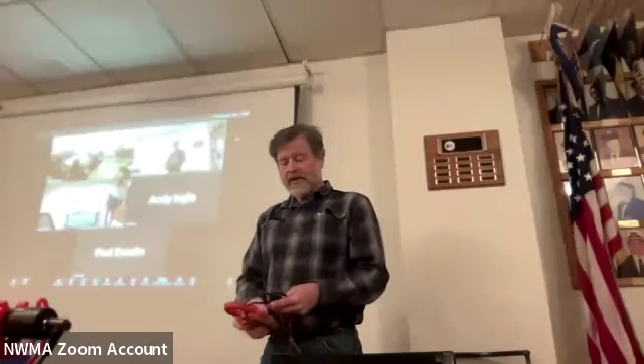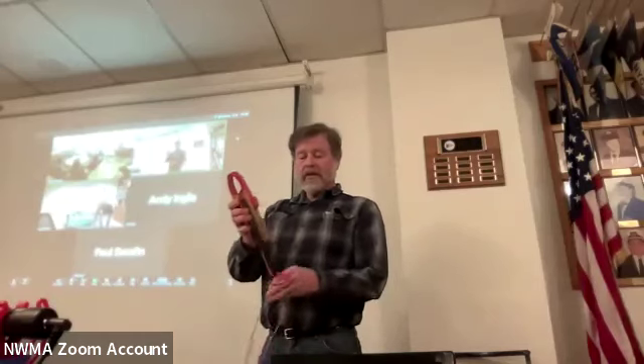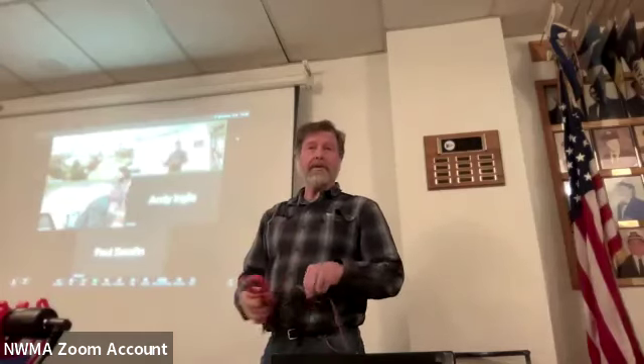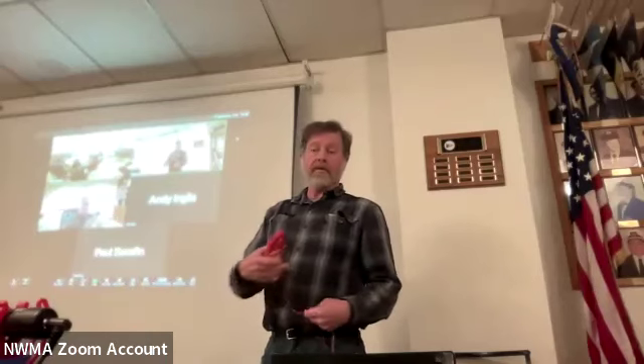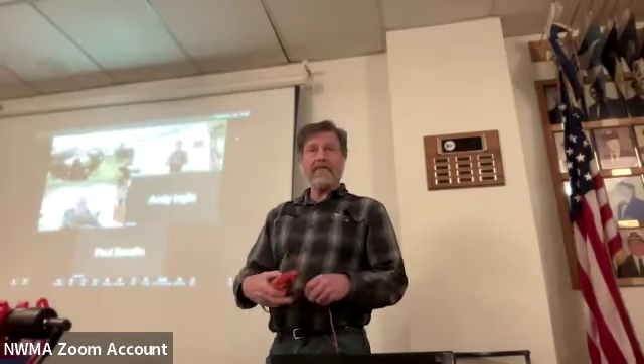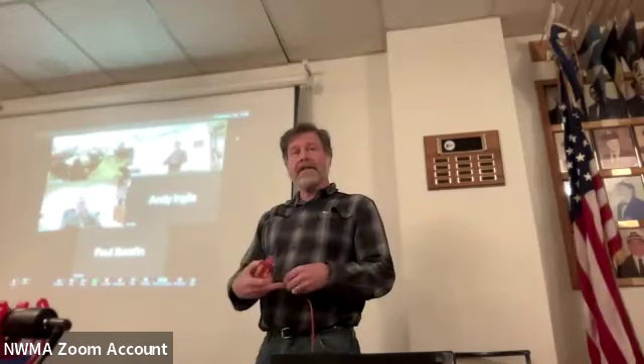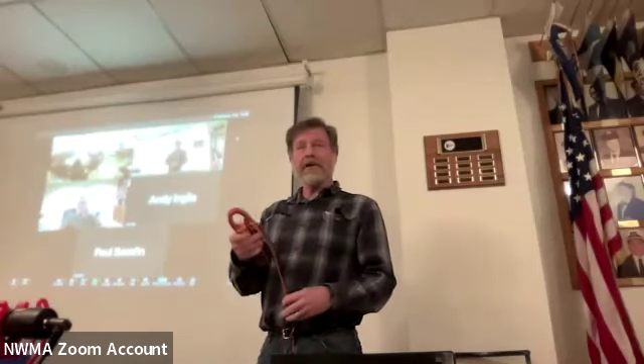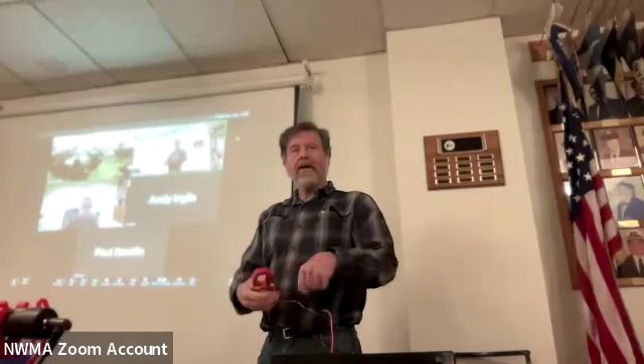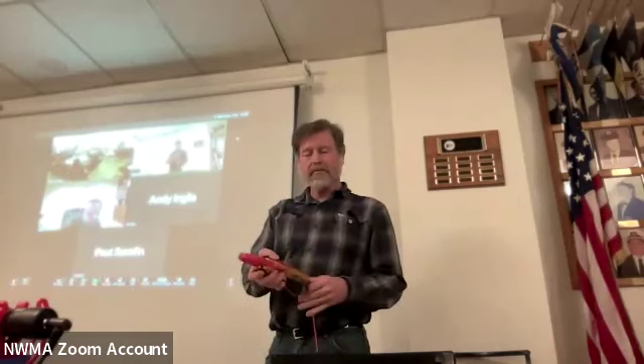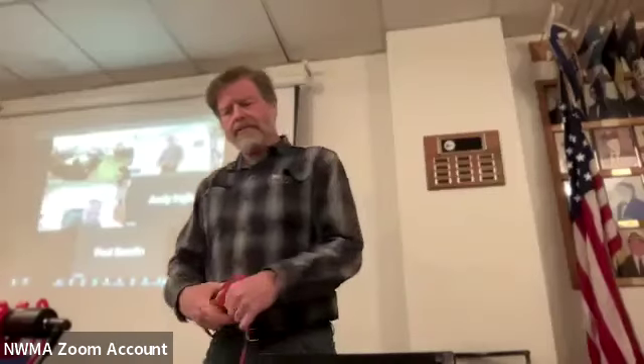We want to make sure we address your question about the big cable going to the windlass. We're going to size the breaker or fuse for that device to protect the wire, and the device will be within that range. But as it gets old, it invariably starts pulling more power, so our safety will be that breaker or fuse. I wouldn't go with an ANL fuse, maybe choose a Class T on that, because it can handle more power, up to 600 amps.